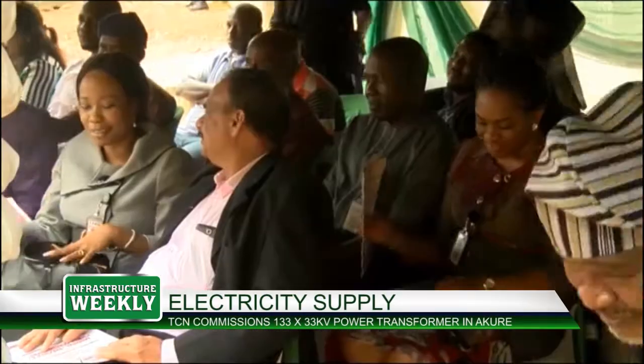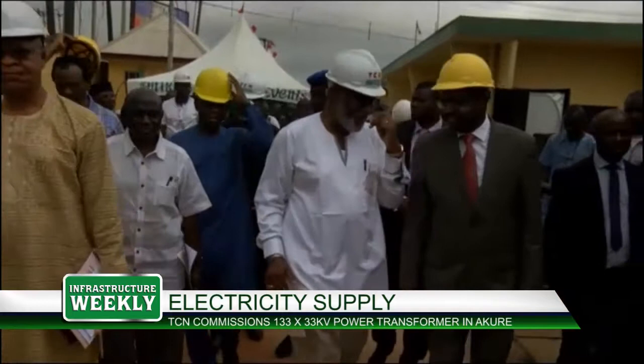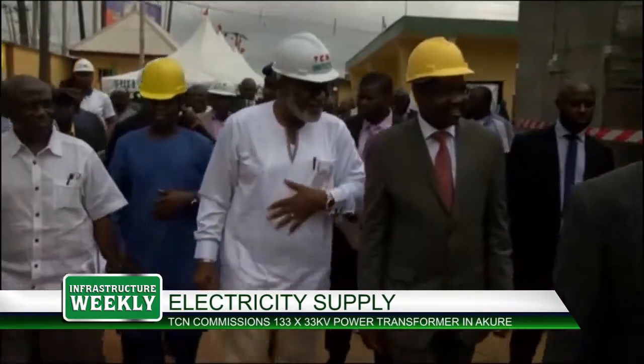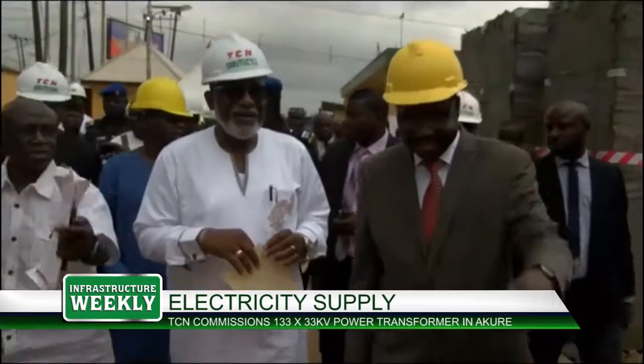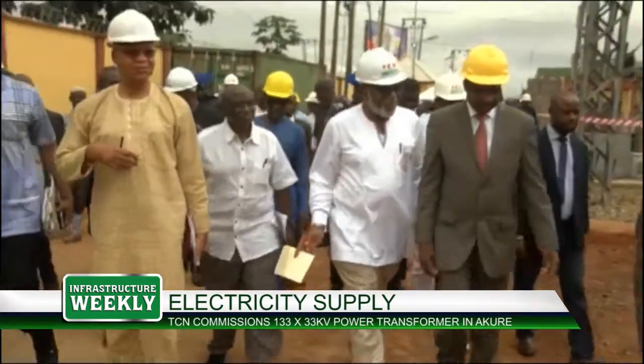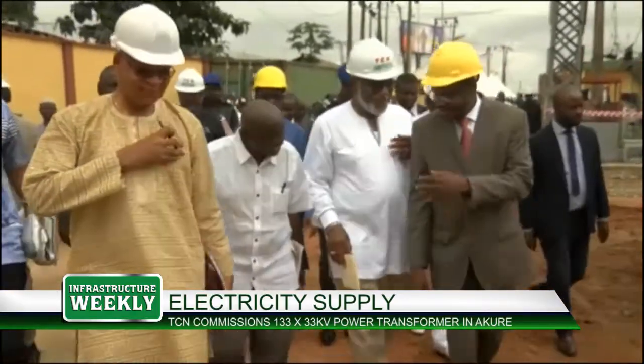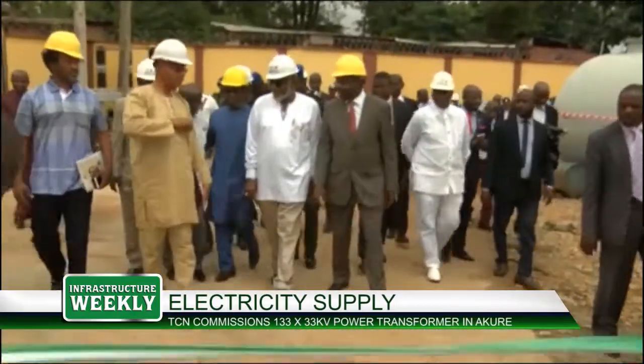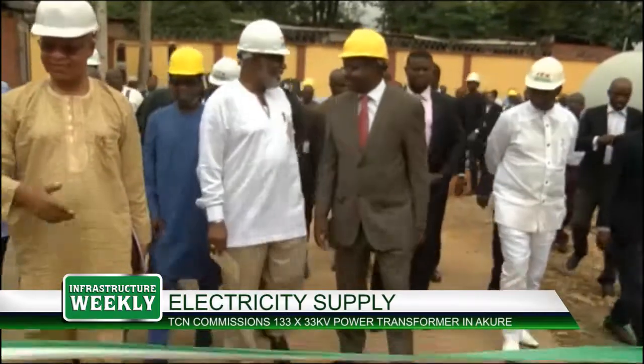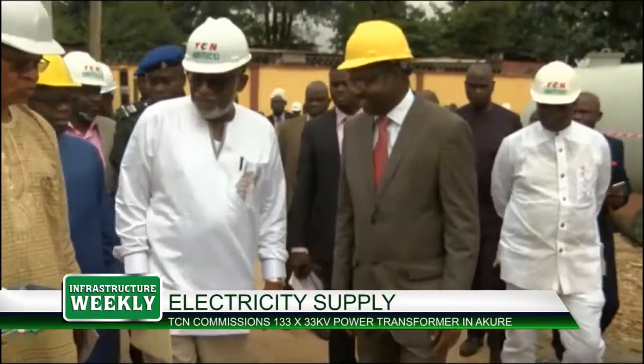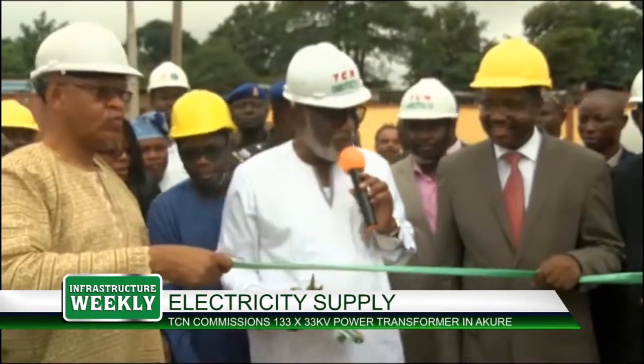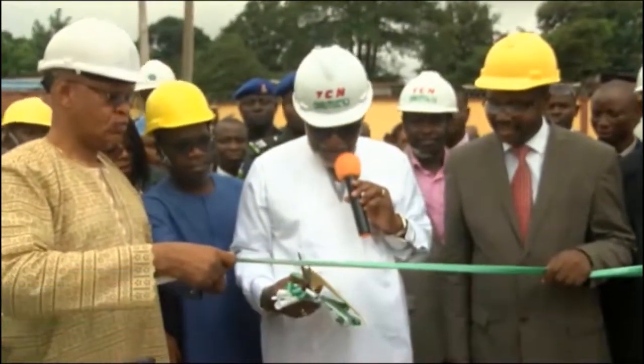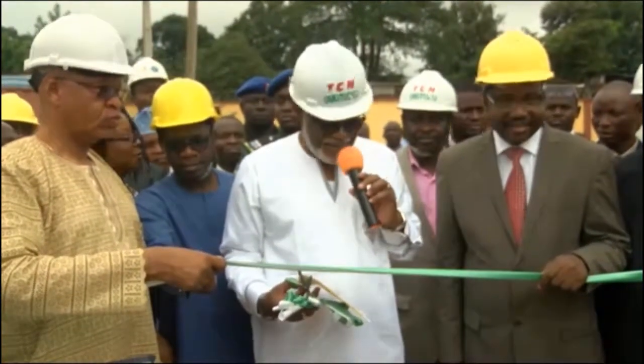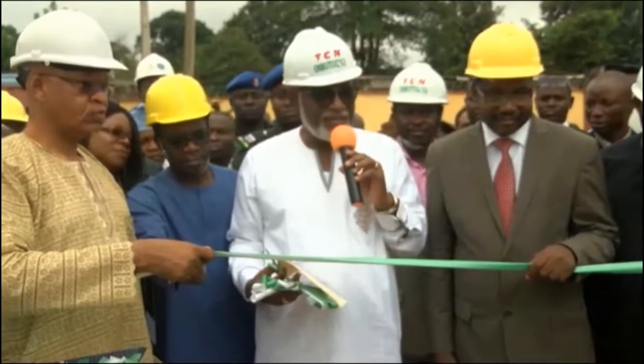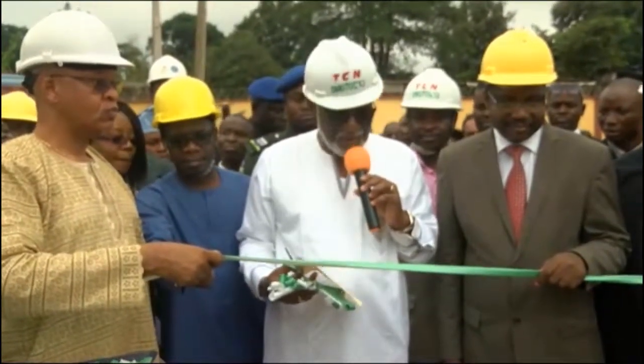In order to strengthen and reinforce the national grid for effective power wheeling and improved service delivery, the Transmission Company of Nigeria earmarked some key transmission lines and substation projects. Akure substation is not exempted, as the existing 132 by 33 kV substation, with initial capacity of 120 MVA or 96 megawatts, became inadequate to meet the required load demand of the growing population and industrialization of the area. This informed the decision to boost the existing power capacity to 180 MVA, that is 144 megawatts.